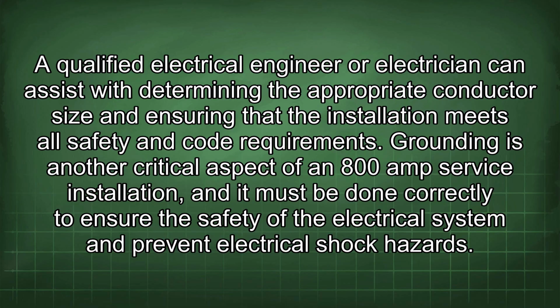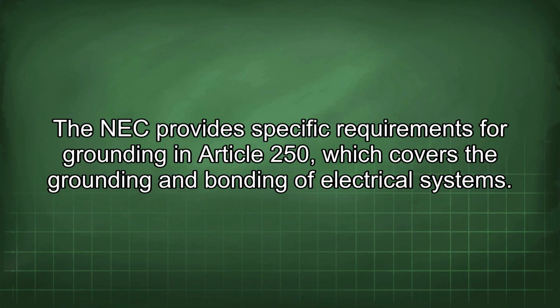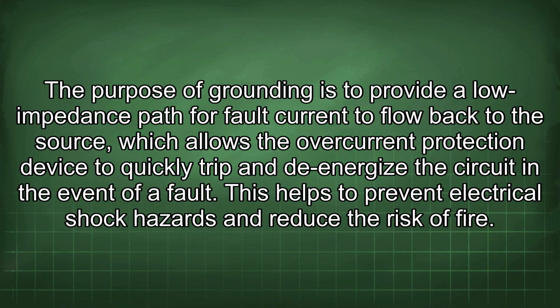Grounding is another critical aspect of an 800 amp service installation, and it must be done correctly to ensure the safety of the electrical system and prevent electrical shock hazards. The NEC provides specific requirements for grounding in Article 250, which covers the grounding and bonding of electrical systems. The purpose of grounding is to provide a low impedance path for fault current to flow back to the source, which allows the overcurrent protection device to quickly trip and de-energize the circuit in the event of a fault. This helps to prevent electrical shock hazards and reduce the risk of fire.